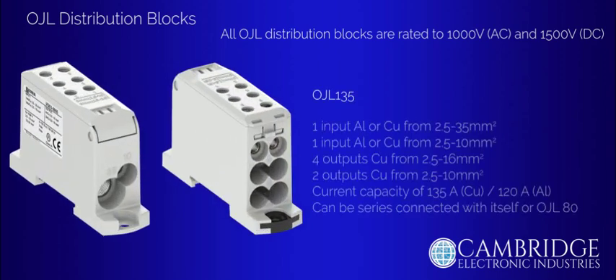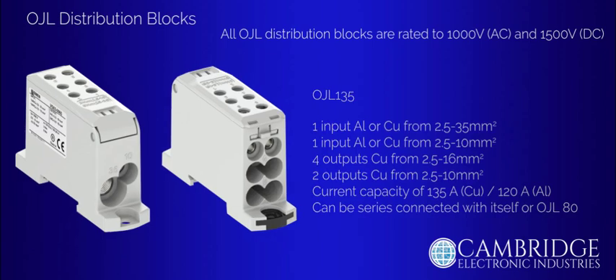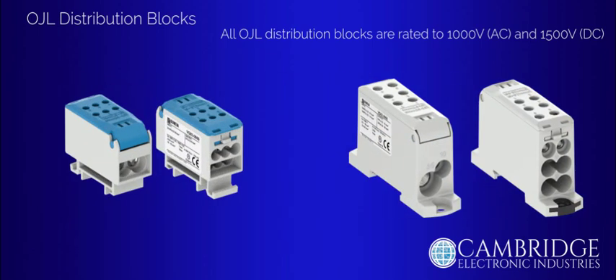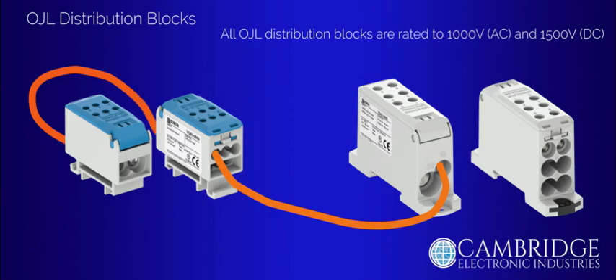OJL 135, as the name suggests, offers 135 amps for copper cable input and 120 amps for aluminium cables. There are 2 input contacts on the distribution block in 2 different formats. There are 6 output contacts in total, which are broken down into 4 outputs for up to 16mm square cables and 2 outputs for up to 10mm square cables. The OJL 135 blocks can be screw or DIN rail mounted and feature the click set mounting mechanism. They are available in transparent top covers and also PA66 covers in black, grey, blue and green. The OJL 80 and 135 can be series connected with each other or themselves.